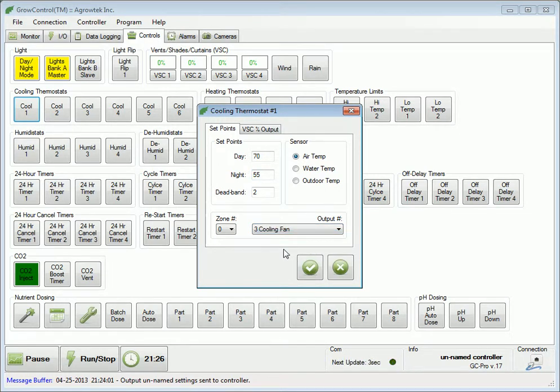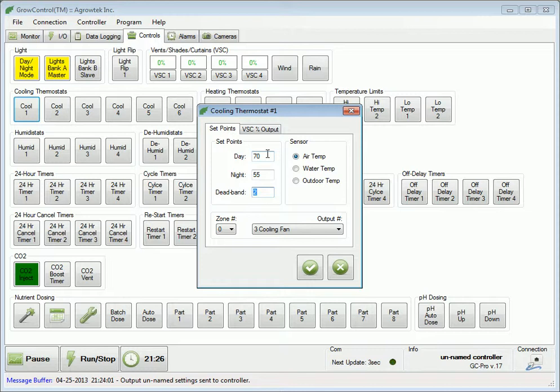Once the cooling thermostat has been activated, it will continue to cool until the temperature has fallen below the set point by the dead band amount. In this case, the temperature will be regulated between 70 and 68 degrees during the day, and 55 and 53 degrees at night.